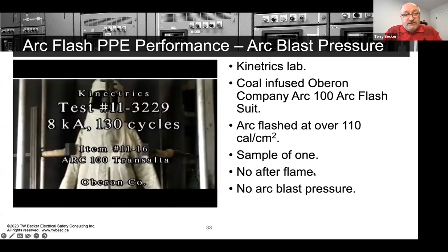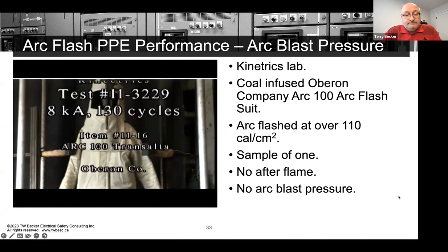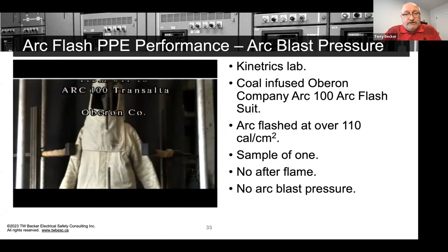Now, in this case, this video is a coal-infused arc flash suit test from a coal-fired power plant. TransAlta, who gave me the video, allows me to use it. And so what we were trying to see is if the coal dust would cause a degradation in performance of the arc flash suit. So we're looking for sustained afterburn, afterflaming on the garment.